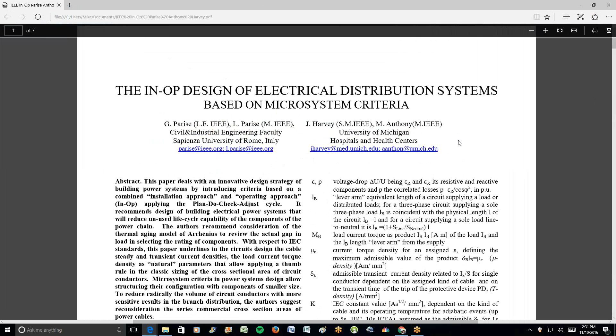So what I'm trying to do is I've collaborated with a colleague in Italy, and he's the knowledgeable one about the scientific basis for the European methods of sizing and designing wires. Continually we run into the Europeans asking us, why are you oversizing your feeder breakers, your feeder circuits? I think it has its origin in the fire safety preoccupation of NFPA, and I do get that, that's the whole history of the NFPA. But if you look at the way that the Europeans approach it, we had to start.